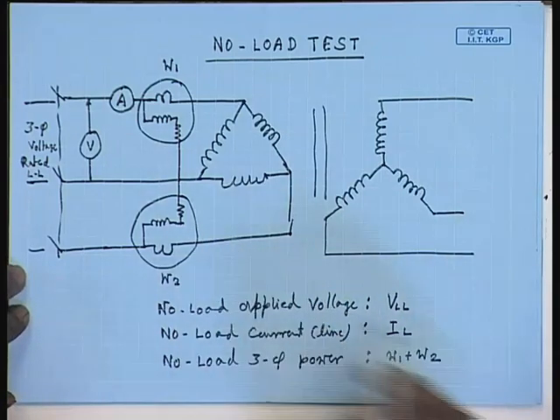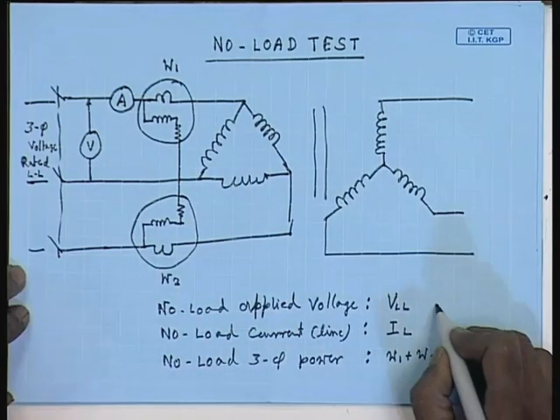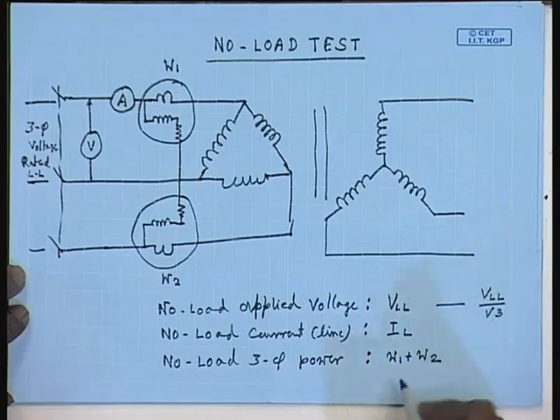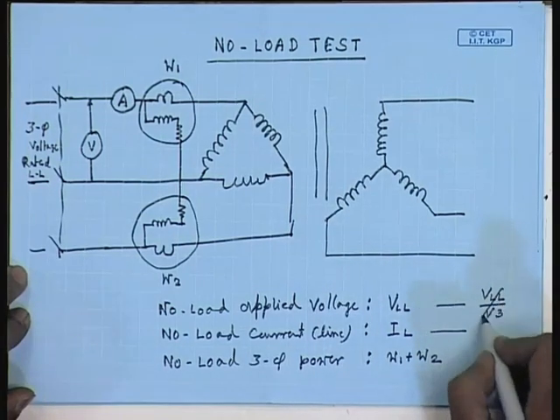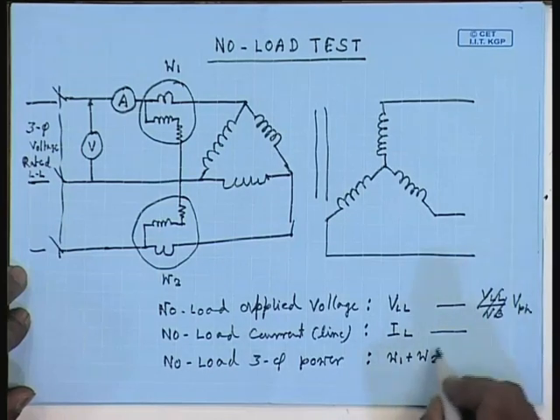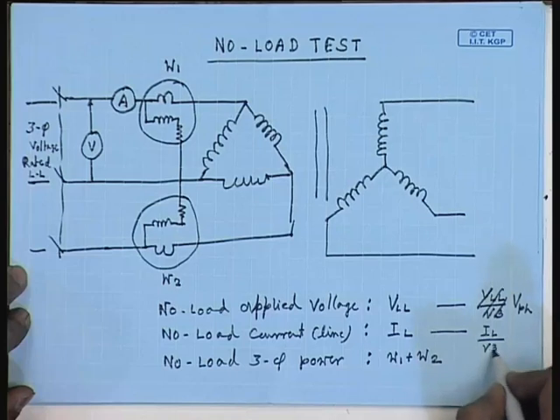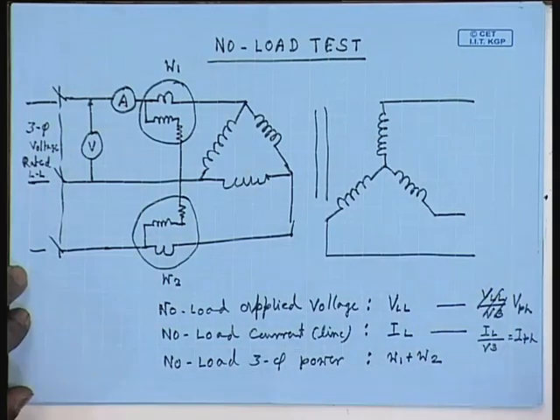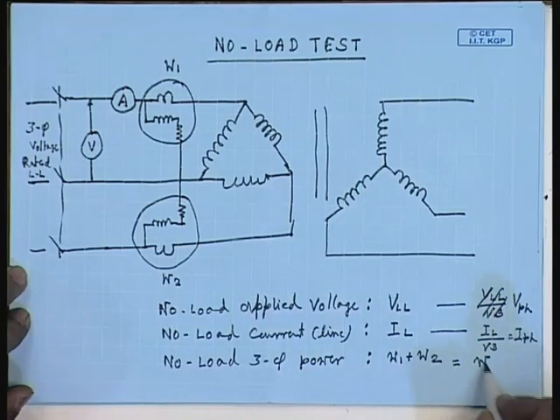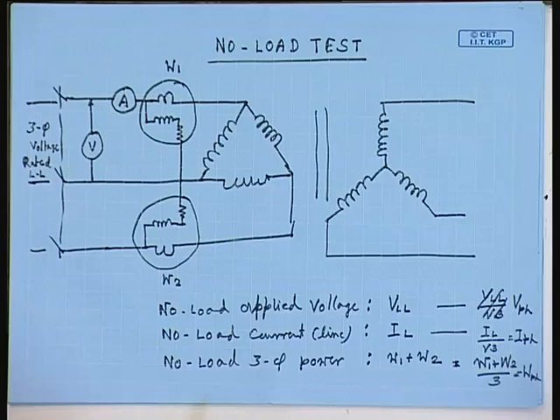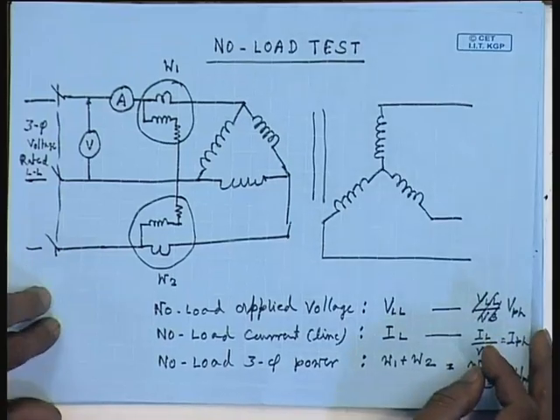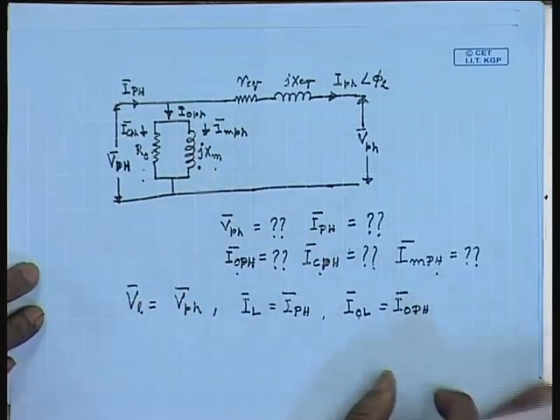Now, depending on the transformer connection, this is delta connected, therefore, the no load applied phase voltage is V_LL by root 3. Sorry, the phase voltage is same as V_LL. The phase current is I_L by root 3, this is equal to I phase, no load phase or winding current, and the no load phase power is W1 plus W2 by 3, this is equal to W phase. So, once we have converted this no load test data to phase quantities, then this can be used in a similar manner as in a single phase transformer to find out the shunt branch components of the per phase equivalent circuit, that is R_0 and X_m.